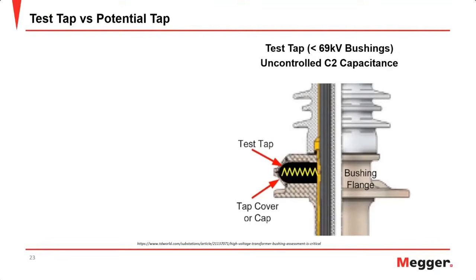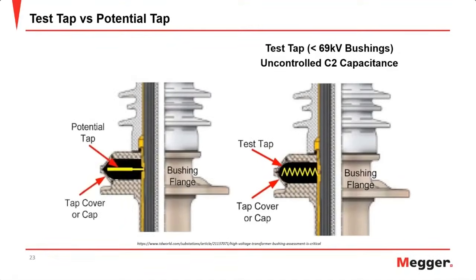And then when we get into the higher voltage bushings above 69 kV, this is called a potential tap. The reason why this is called a potential tap instead of a test tap is because instead of being connected directly to the last layer, the potential tap is connected to the second to last layer, and then the last layer is connected directly to ground.